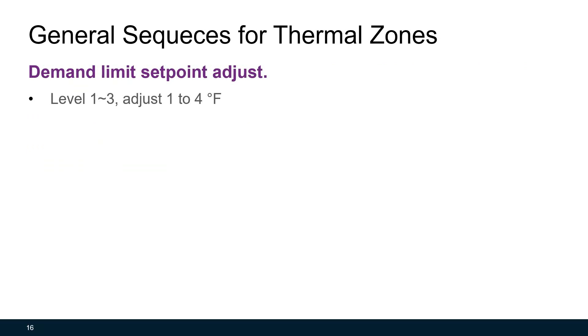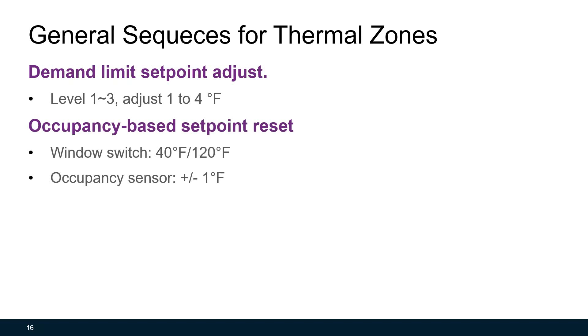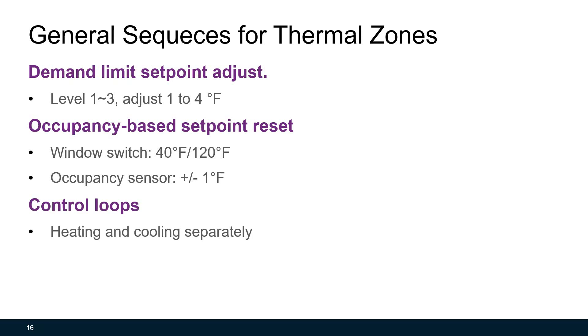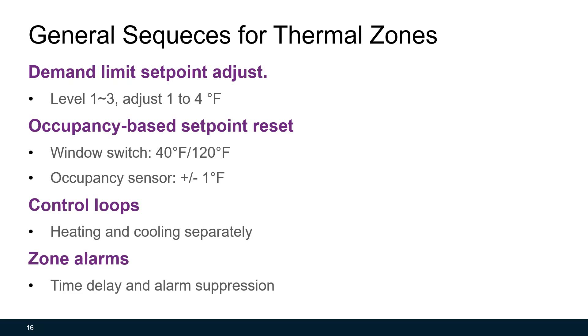General sequences for thermal zones include the following. For peak demand reduction, the guideline defines three demand limit levels; the zone cooling set point can be adjusted by 1 to 4 degrees F. If operable windows are open, the zone heating set point should be temporarily set to 40°F and cooling set point to 120°F. If an occupancy sensor indicates no occupant, the zone heating set point should be reset lower by 1 degree and cooling set point higher by 1 degree. For zone temperature control, heating and cooling control loops should be separate.